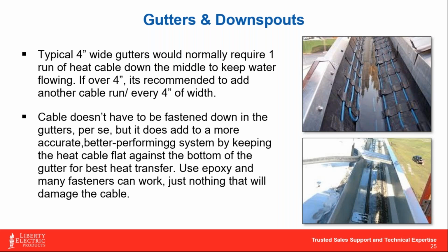A brand new heat cable is going to melt about 2 inches per side when you lay it flat on a surface. So on a 4-inch gutter, if you run a heat cable right down the center, you've got 2 inches per side, and you've got the whole bottom surface area pretty well covered. But in an 8-inch wide gutter, the heat's not getting all the way out to each edge. You'll be melting nicely in the middle, but you're going to gang up some ice around the edges where you're not getting heat to.